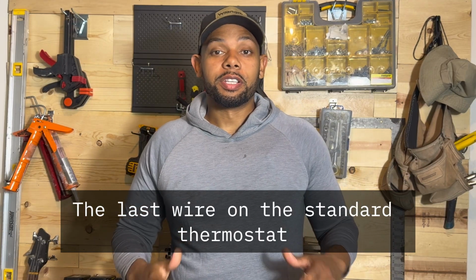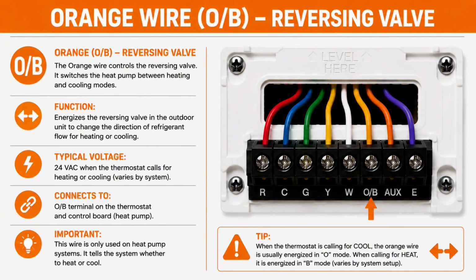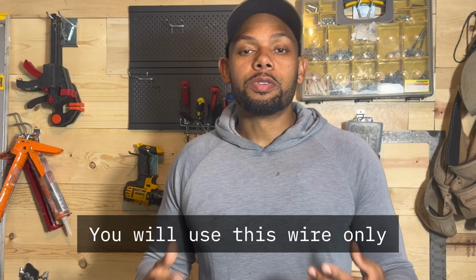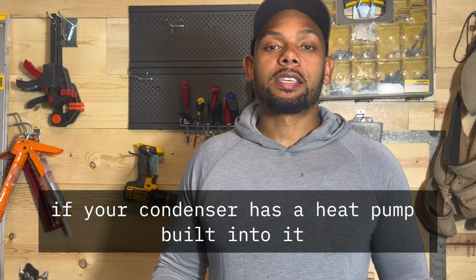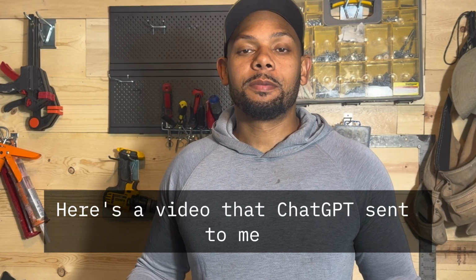The last wire on the standard thermostat, the orange wire, is commonly used for a heat pump system to control the reversing valve. The reversing valve changes the direction of refrigerant flow, allowing the heat pump to switch between cooling and heating. You will use this wire only if your condenser has a heat pump built into it. So how does a heat pump function? Was a question that I had. Here's a video that ChatGPT sent to me.